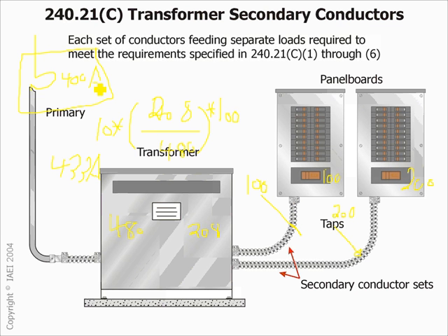So the reason why the guys took the smaller is because that's the worst scenario, right? Smaller is the worst scenario. If it's good for the 100, it's definitely good for the 200. There's no way you feed a 400 amp and final going 300. 480 in, 208 out. No, that's the maximum. What we're just saying? This is the maximum. The maximum. Yeah. There'd be no protection. The maximum to protect this cable. Code doesn't let you go that high anyway.